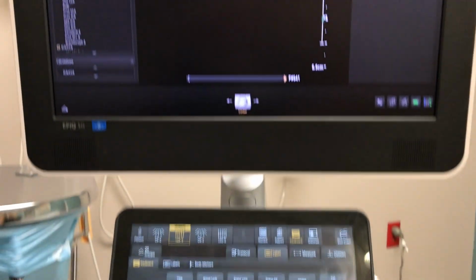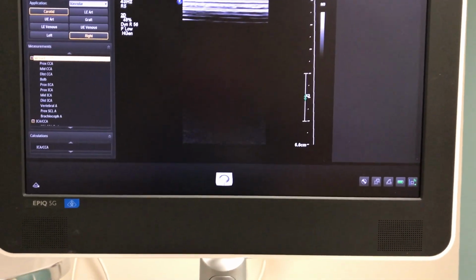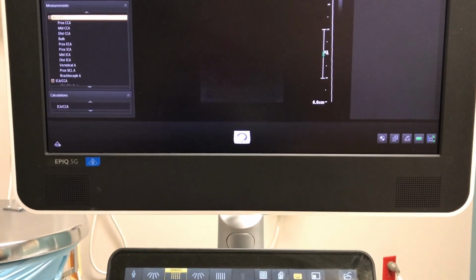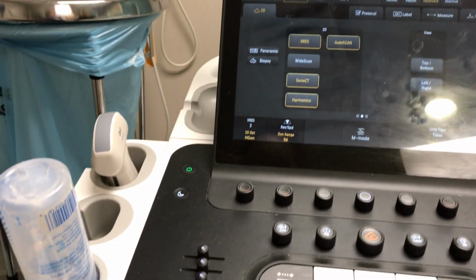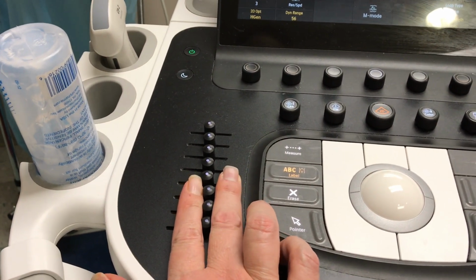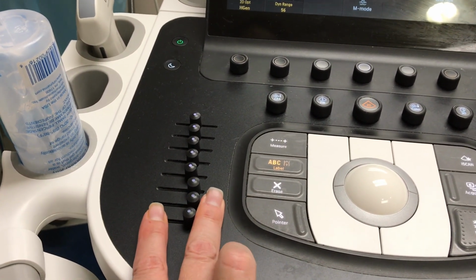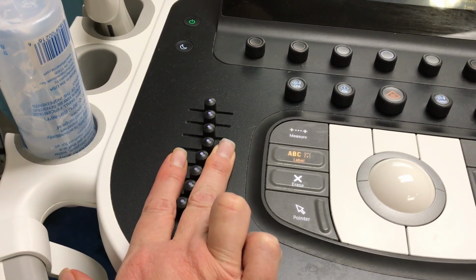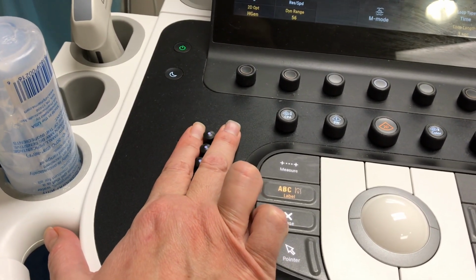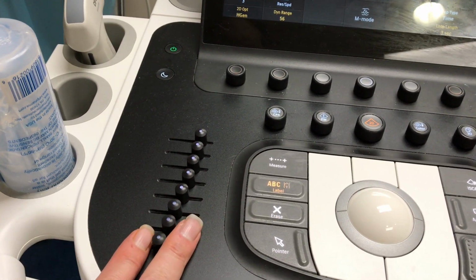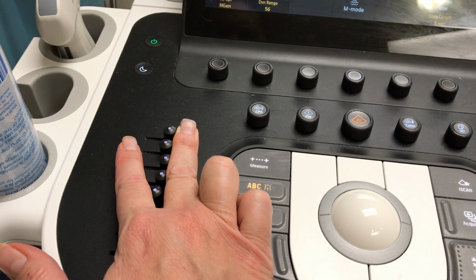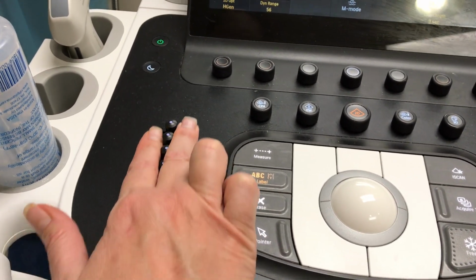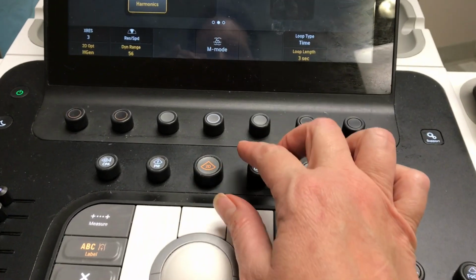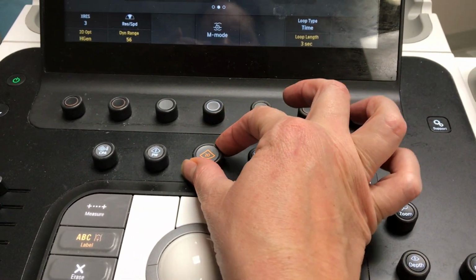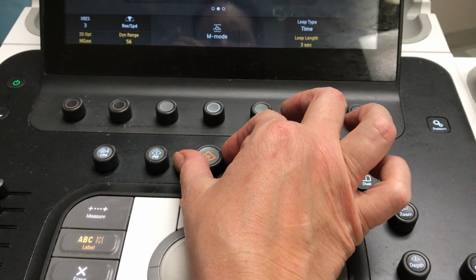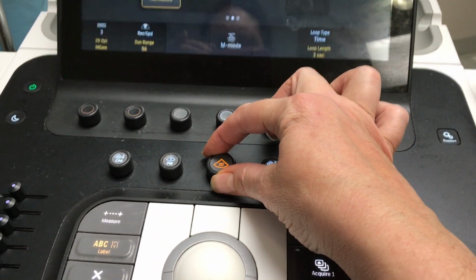When you are imaging and you want to turn the far field brighter, you can use the TGCs. Move them a little brighter, or if you want to make the far field darker, bring them in. If you want the near field to be brighter, turn the TGCs that way, or back for it to be darker. If you want your overall picture to be brighter, then you simply turn this knob, the 2D gain, or back if you want your image to be darker.